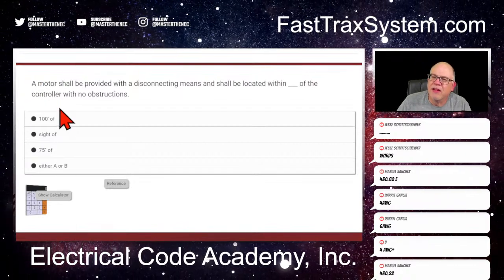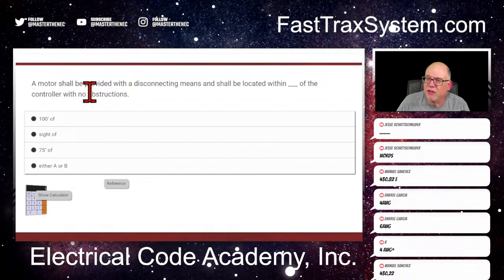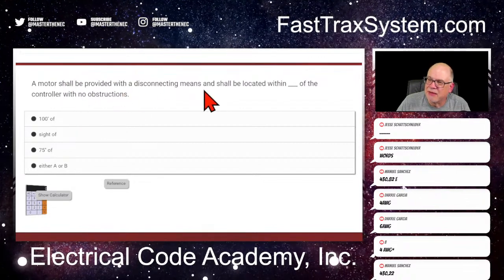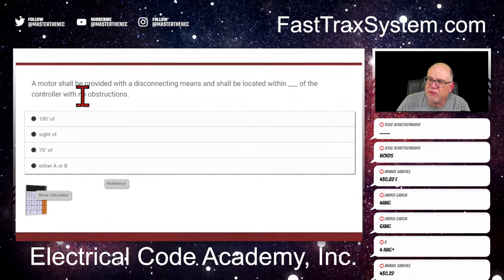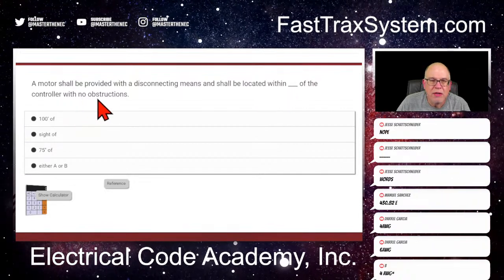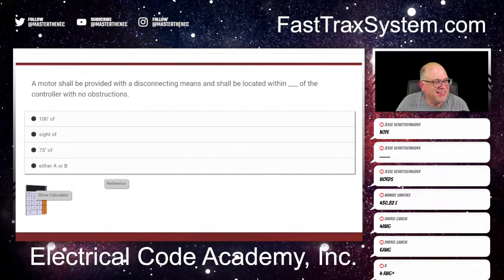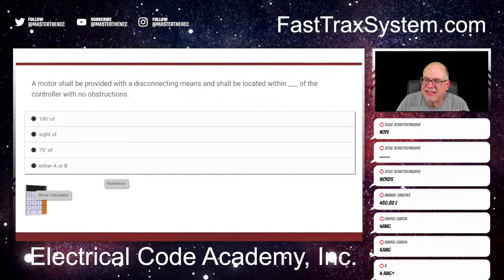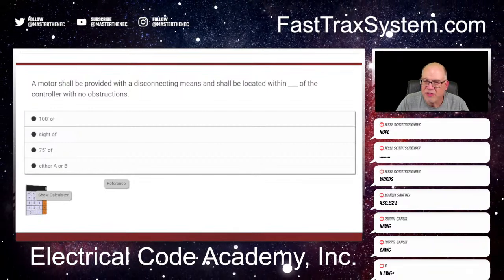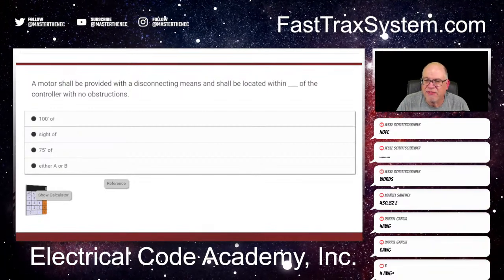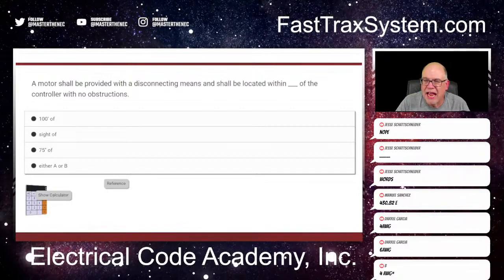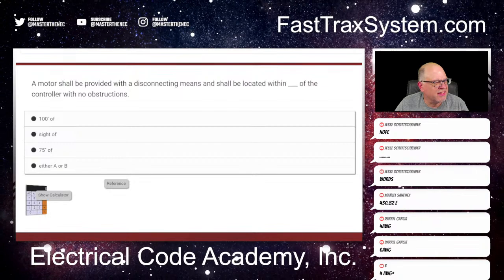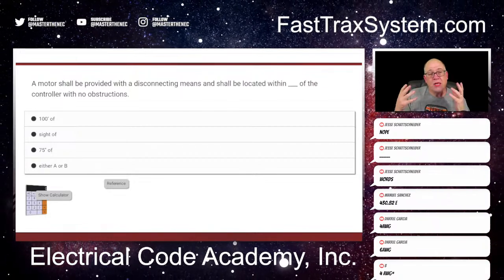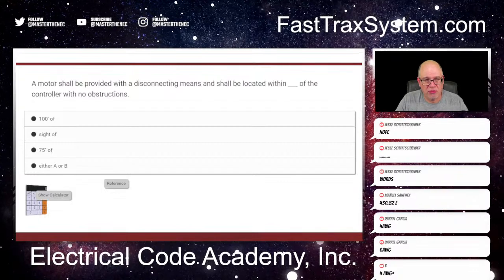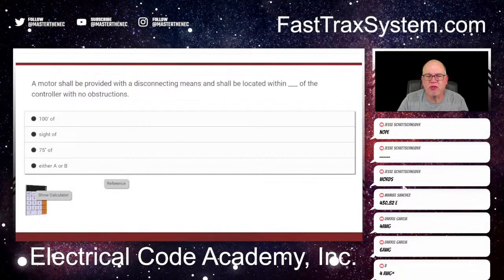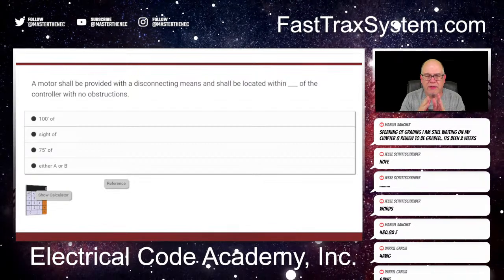All right, it says: a motor, another motor question, shall be provided with a disconnecting means and shall be located within blank of the controller with no obstructions. So what do you think this is? 100 feet? Sight of? 75 feet? Or either A or B? What do you think the answer is? Well, you have to understand what 'within sight' means, and there are two distinct pieces to that.